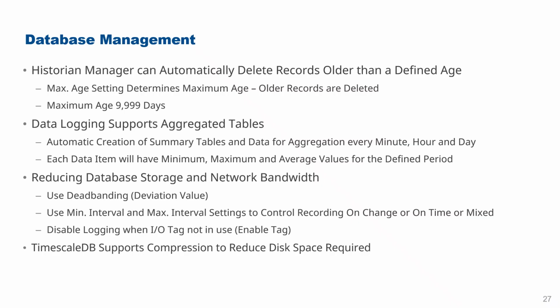Now there's another way of reducing database storage and network bandwidth. First of all, we've got something we call dead banding, and you do this by setting a deviation value. So if you've got an integer value, you might store on change, but in order to avoid sending every single value change, maybe you're recording a level, and the level might be 50% with a value of 50, but some level meters would oscillate between 49 and 51%.